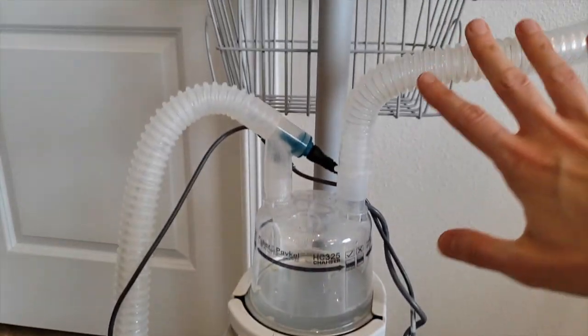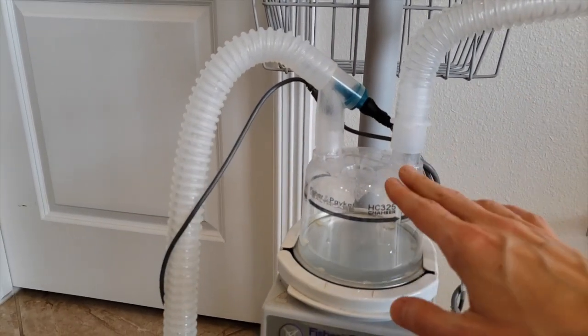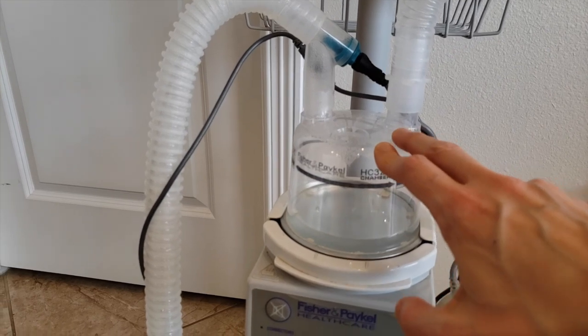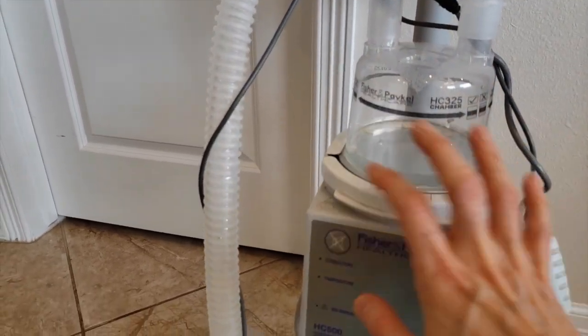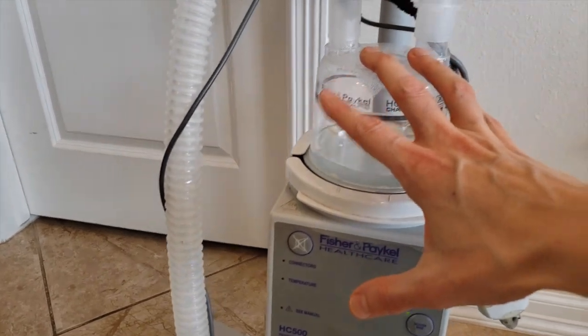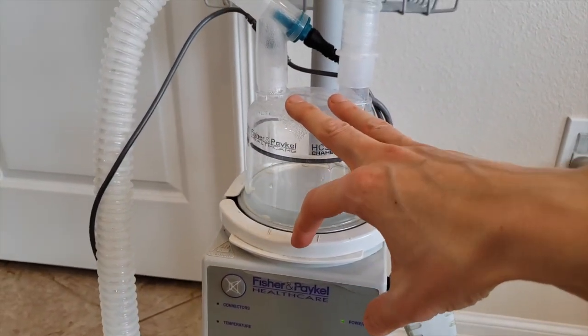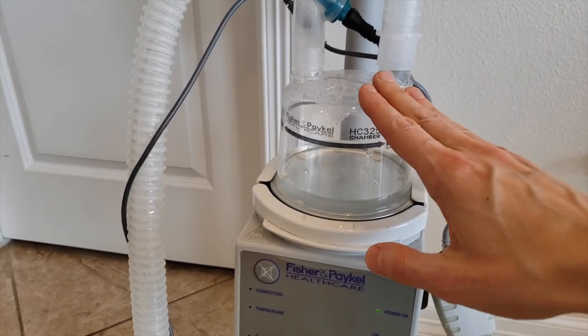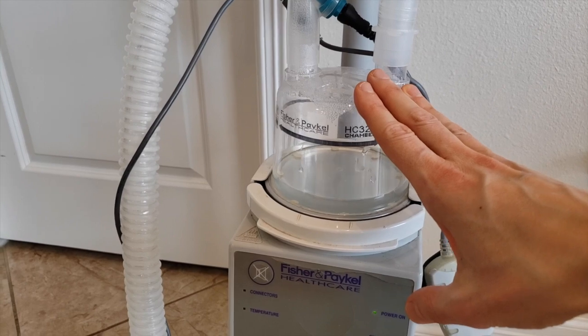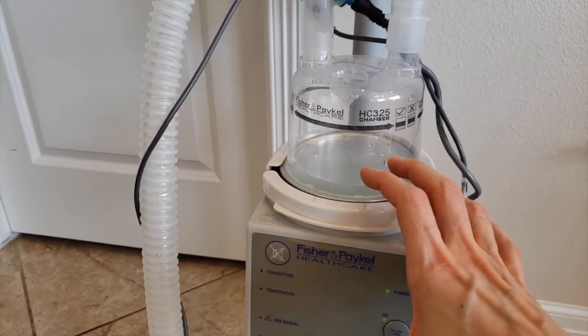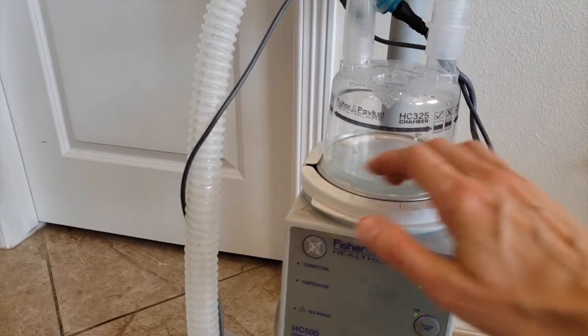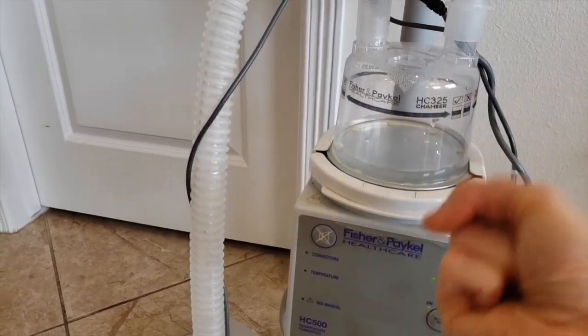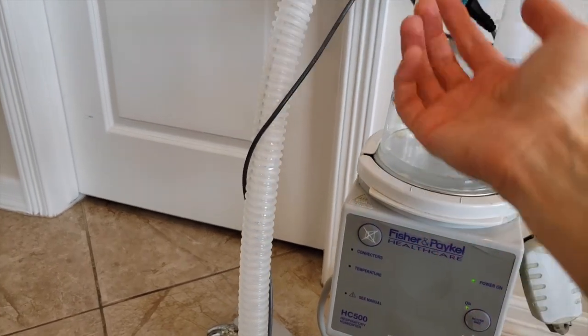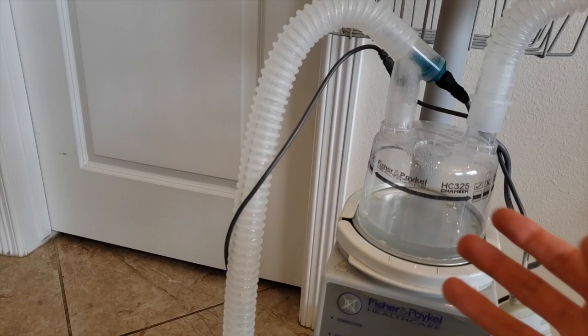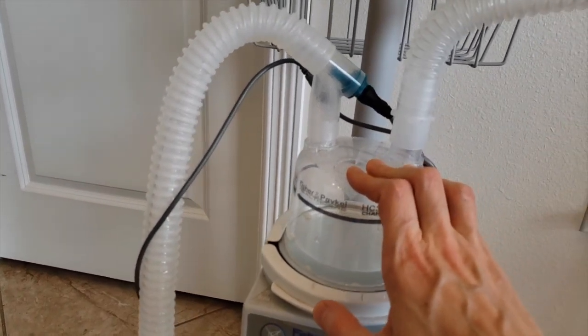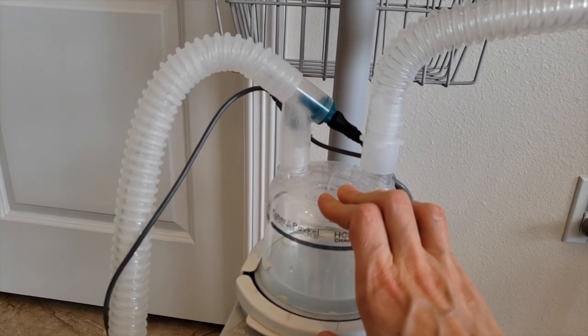So as this room air, which is approximately 68 degrees Fahrenheit or approximately 20 degrees Celsius, as that colder air comes in, it's going to go into this water chamber. It's going to get heated up. If you know anything about the properties of air and the amount of water it can hold, warmer air can hold more water than colder air. So as the air hits this hot water, the air will be heated. It can hold more water. It will increase the moisture. The moisture will go into this tubing. This warmer, moist air will enter the airways, and that will prevent the airways from drying out.